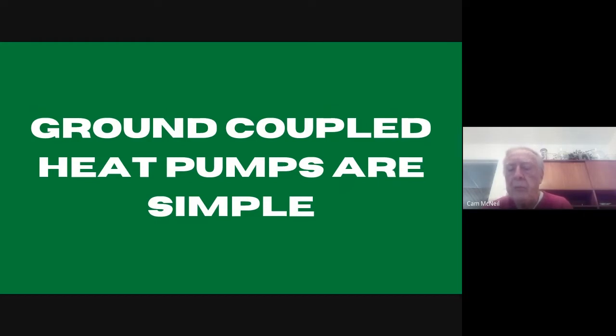A ground source heat pump, or ground coupled heat pump, moves heat from the ground into the building and raises its temperature. The ground collector is usually buried polyethylene pipe filled with water and antifreeze, or well water, which circulates through the heat pump. The compressor, located safely inside the building, converts this energy into usable hot air or hot water very efficiently. Cooling is done by reversing the energy flow.